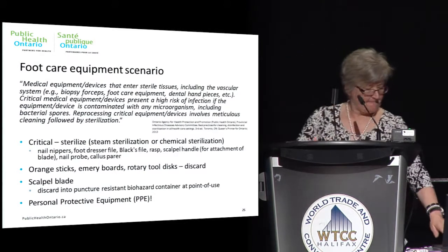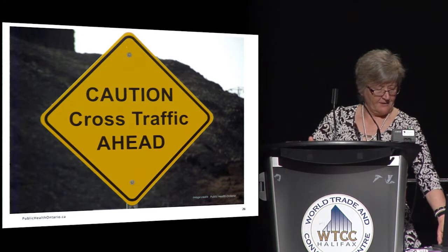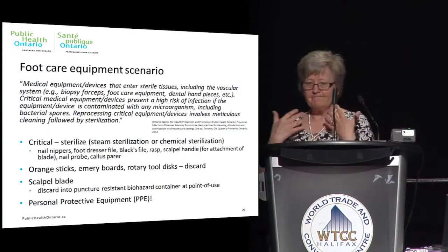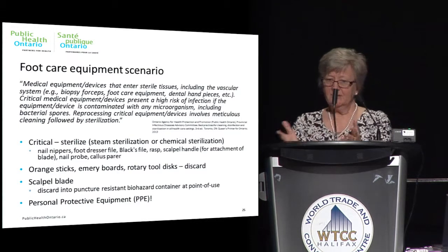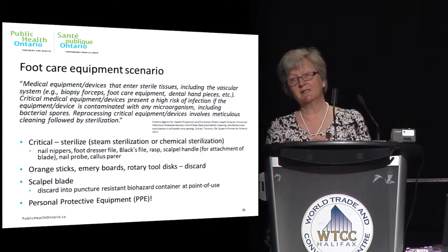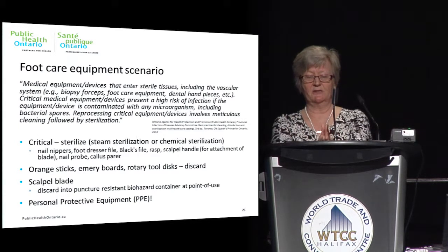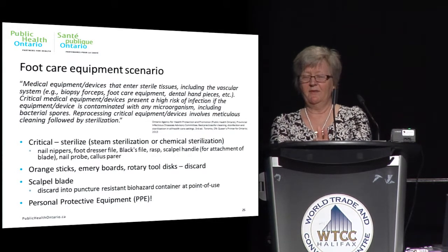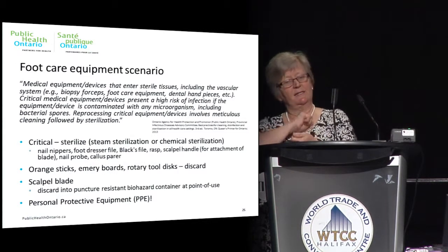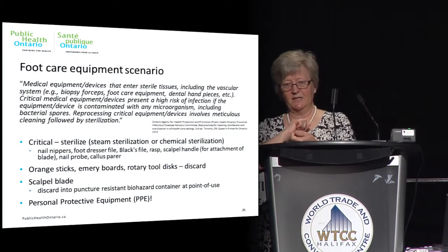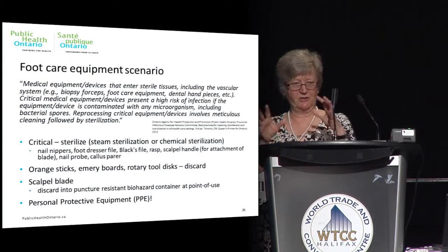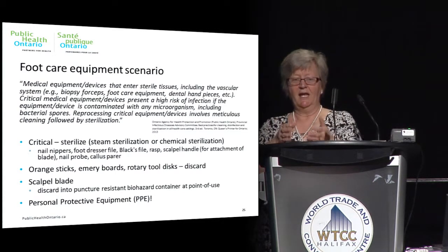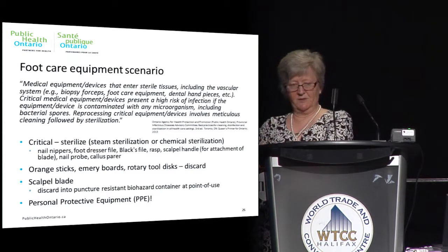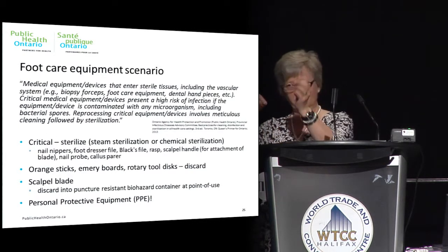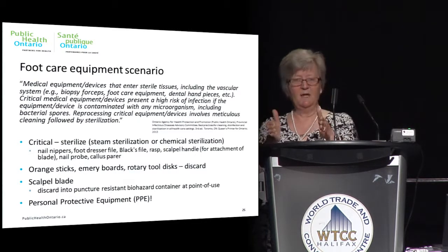And I just want to go to the cross traffic that we can run into with making decisions as agencies about how you would reprocess something like foot care equipment. And many are still doing a liquid chemical sterilization. And the piece with that is of course the items would have to be cleaned with the detergent or the enzymatic or whatever initially, and brushed and rinsed and dried, and then put into the liquid chemical sterilant that meets all the standards, and with the test strips it would meet it for the amount of contact time that's required.